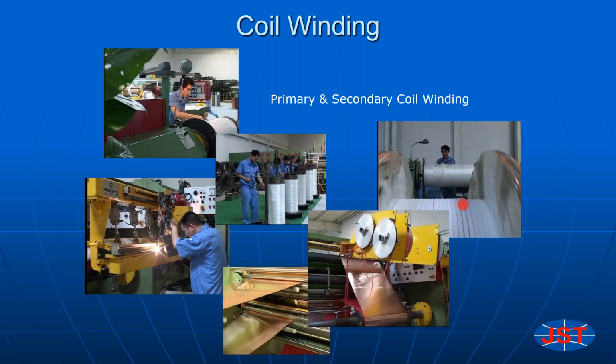But we do manufacture our own wire. We get the extrusions, draw it through a die, and then we wrap it with a special grade crepe paper that we specify for its absorptive properties. That's wrapped on a mandrel, and there's a lot of tension controls, again, to keep the right uniformity and integrity that we're going to need for the winding.